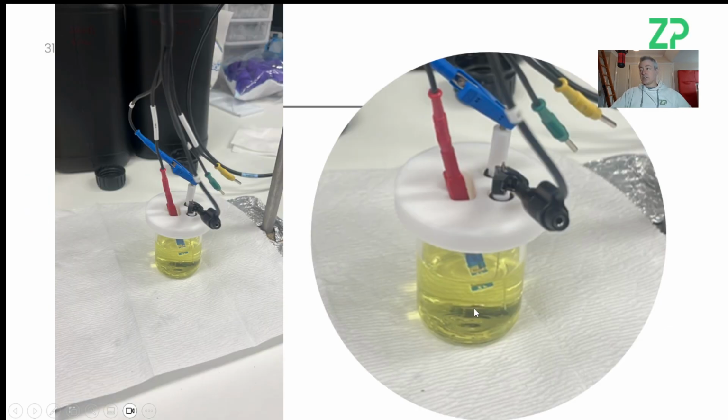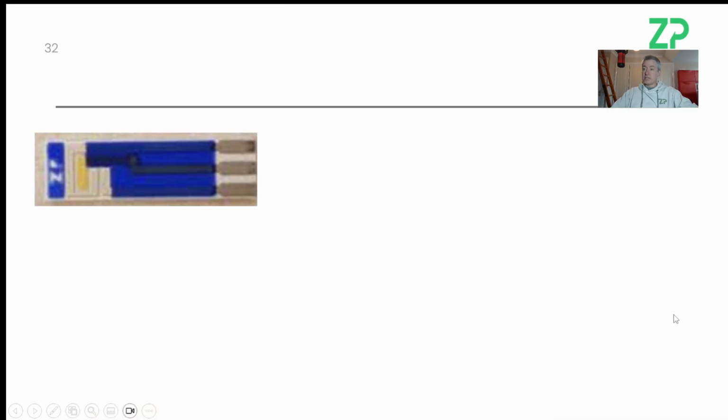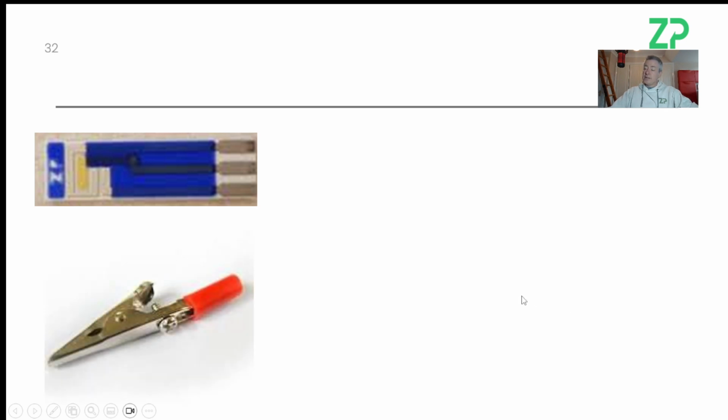So I think it just comes down to, at a minimum, you've got a connection problem. You may even have a potentiostat problem. The potentiostat's harder for me to solve because that's a third-party instrument. But I think primarily the problem is actually your connection. So what you're trying to do is clip onto this here using this guy. There may even be a case that you're actually making liquid contact with this crocodile clip, with a liquid solution, that is.